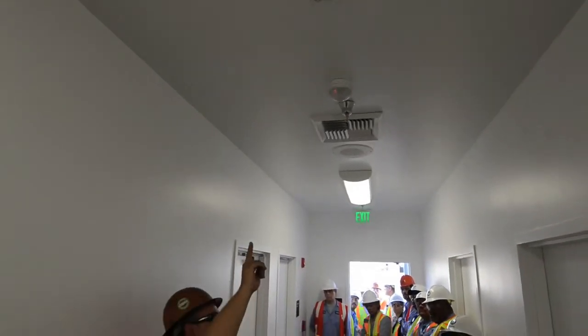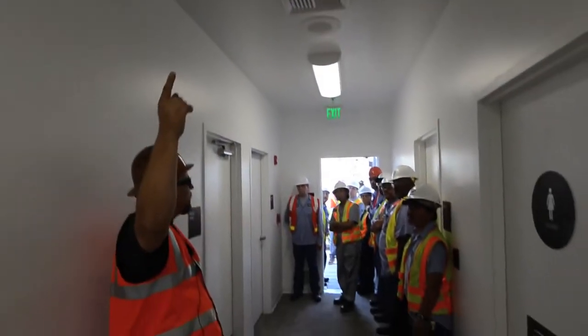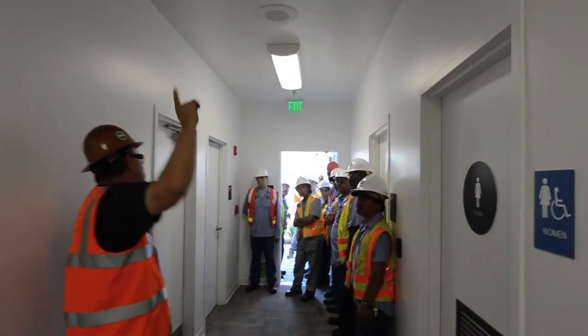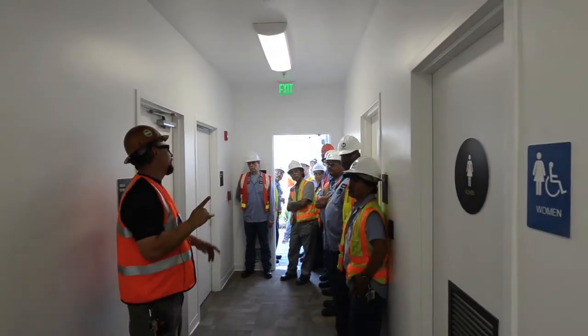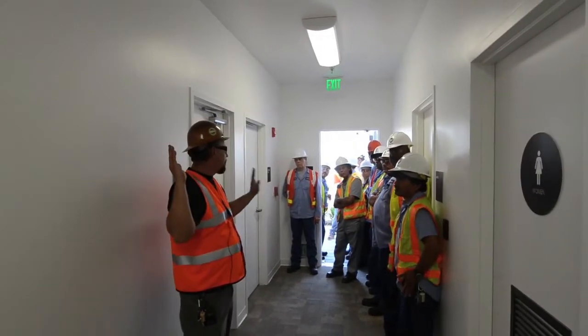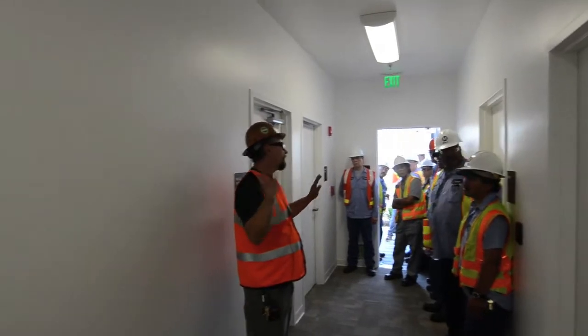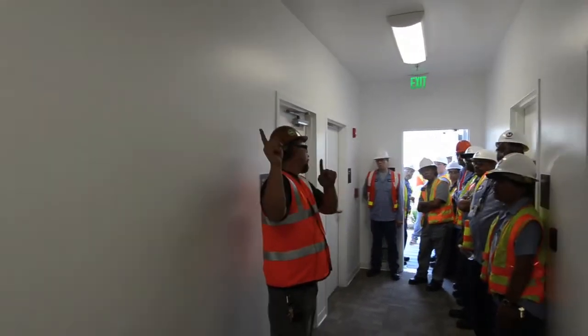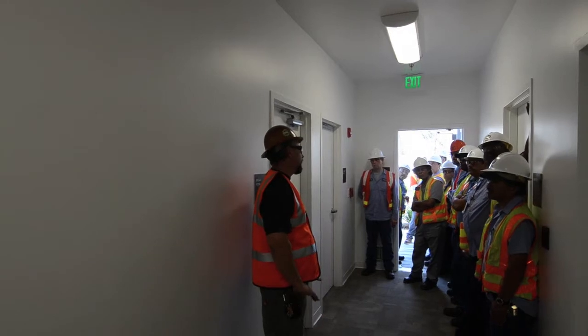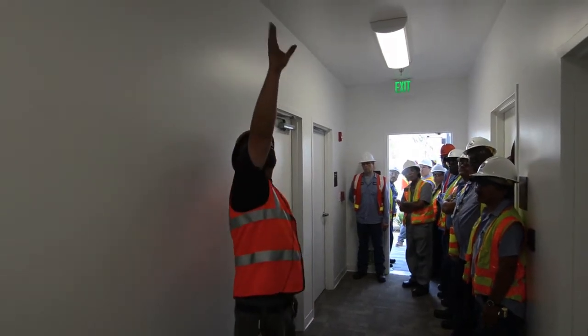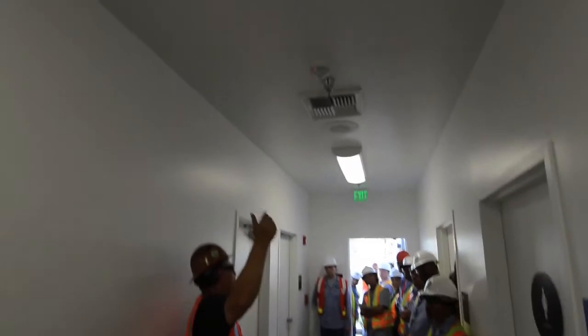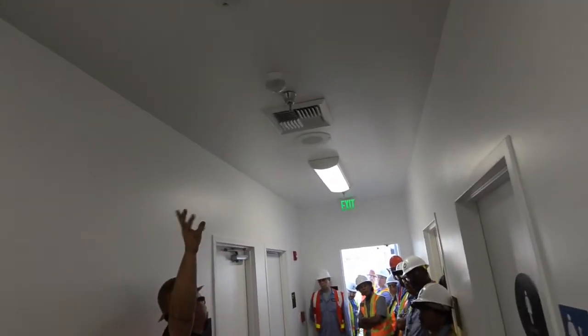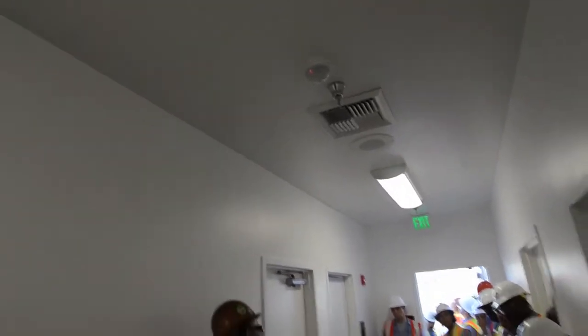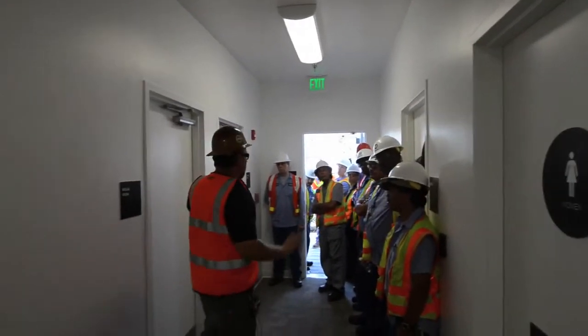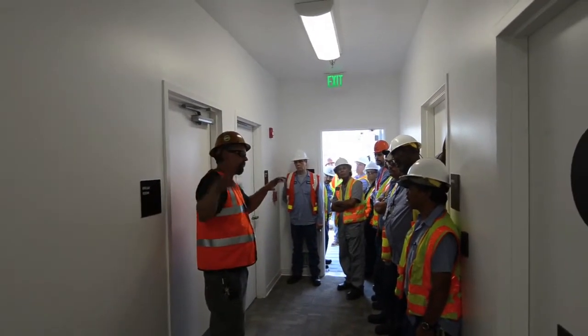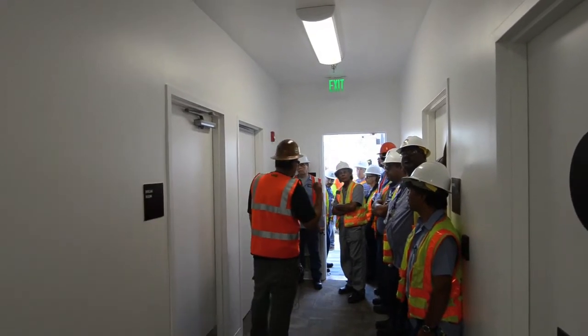You've got two sensors in this hallway, one for normal power and one for emergency power. What those do is just turn off one light per emergency and normal power circuit when nobody's moving in the hallway. Those are not part of the lighting control system, they're separate. It's just a switch. If you pull that down, you've got a hot and a switch leg leaving out to a light next to it. They're not part of the lighting control system. It's just so that when people aren't moving around in here, it turns a couple lights off, basically. But only one per sensor.